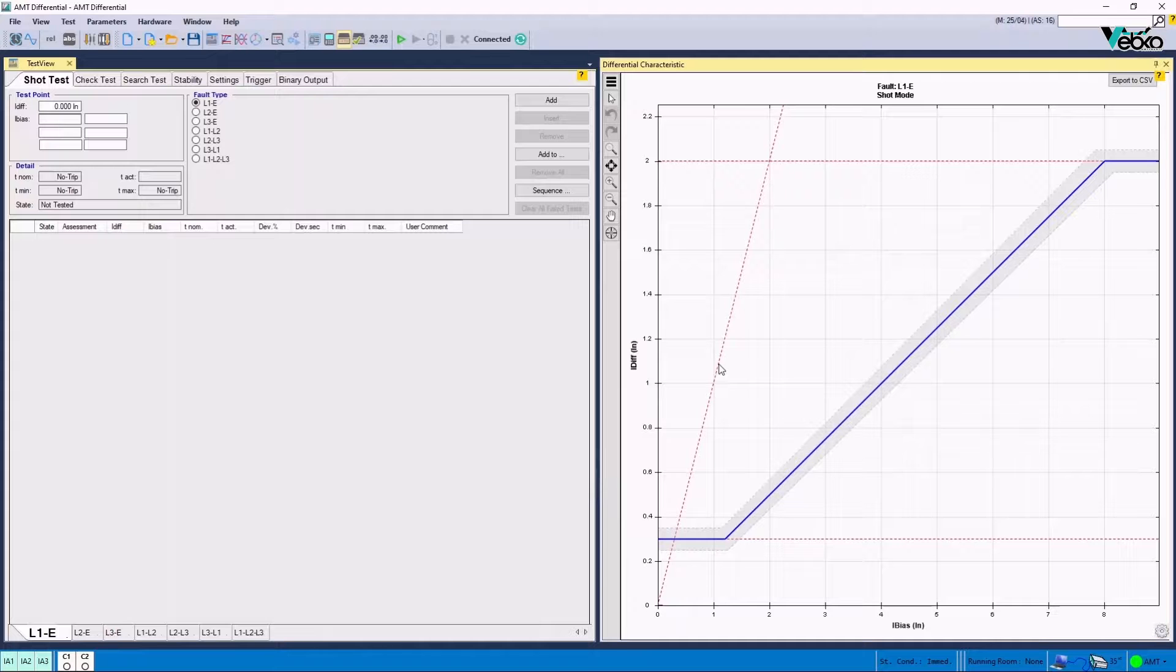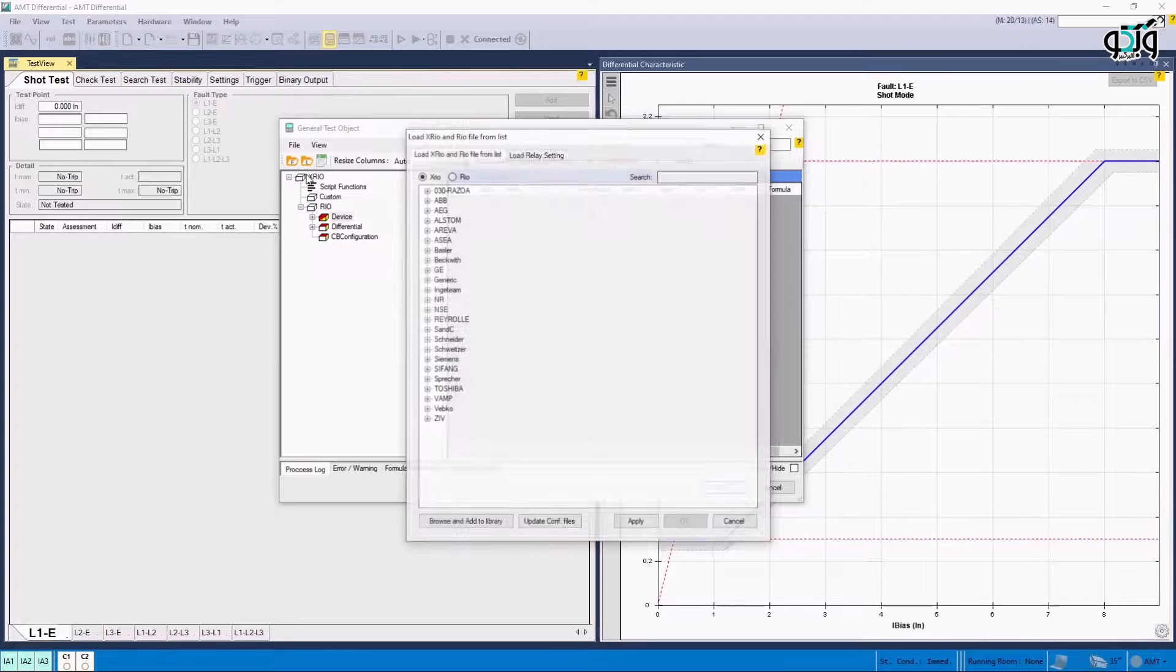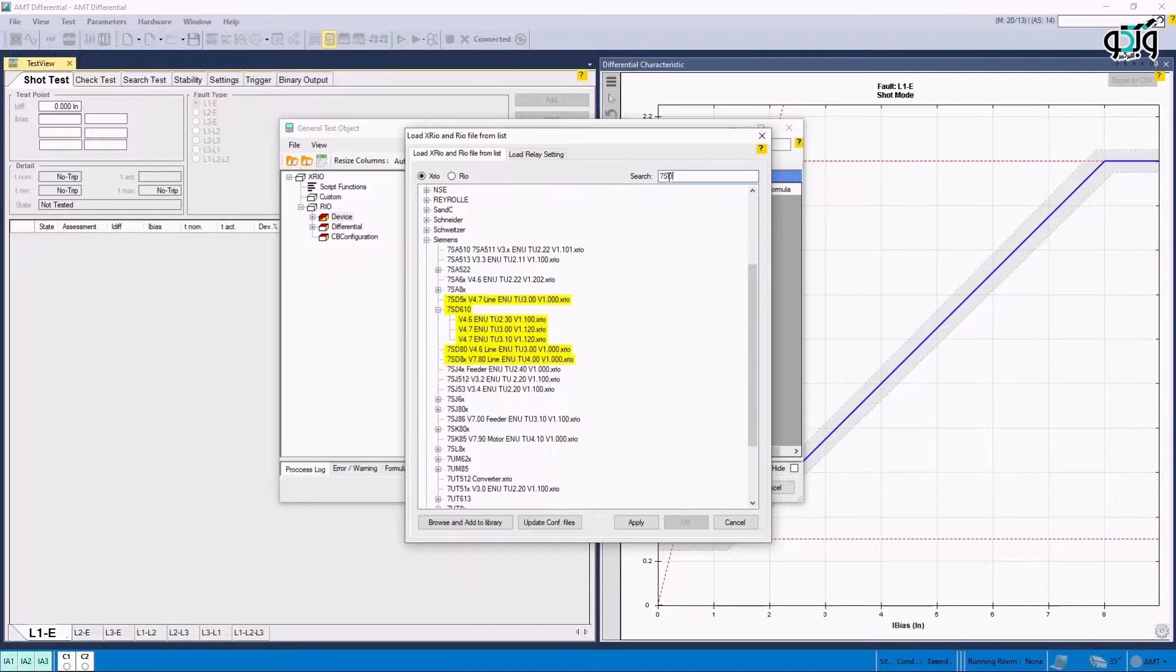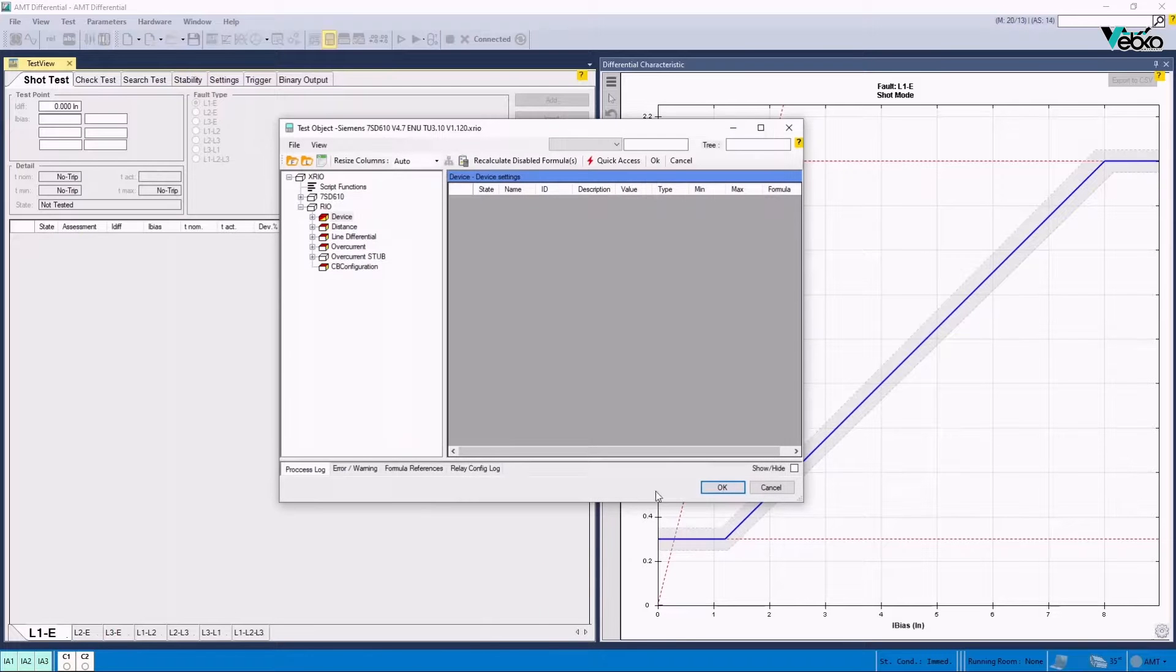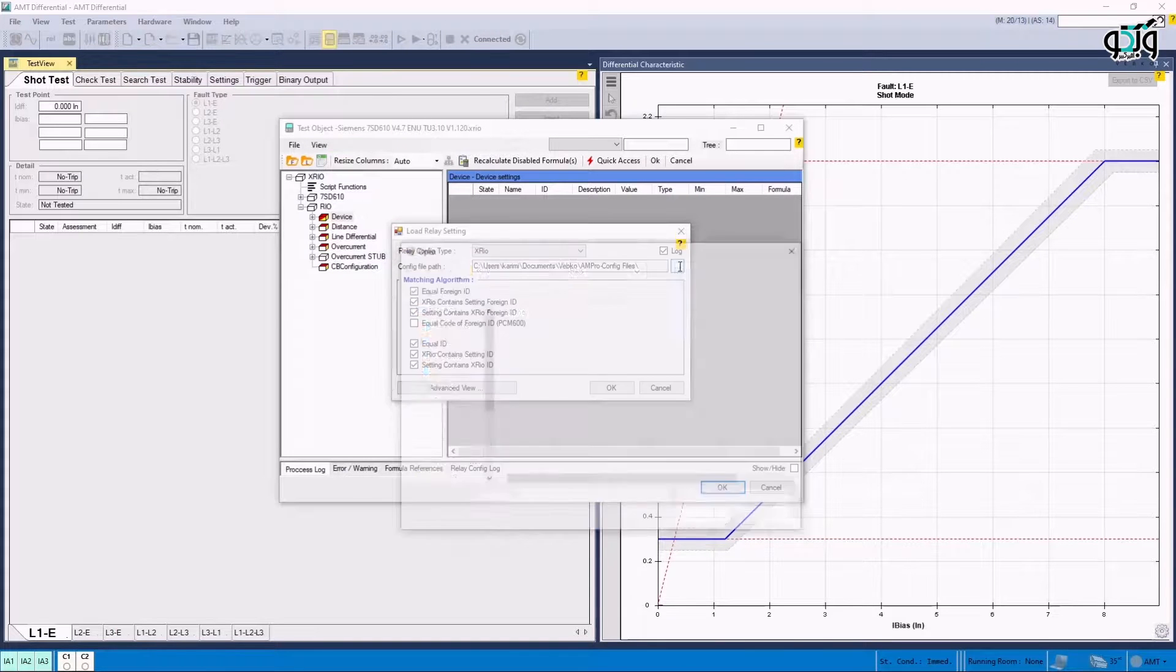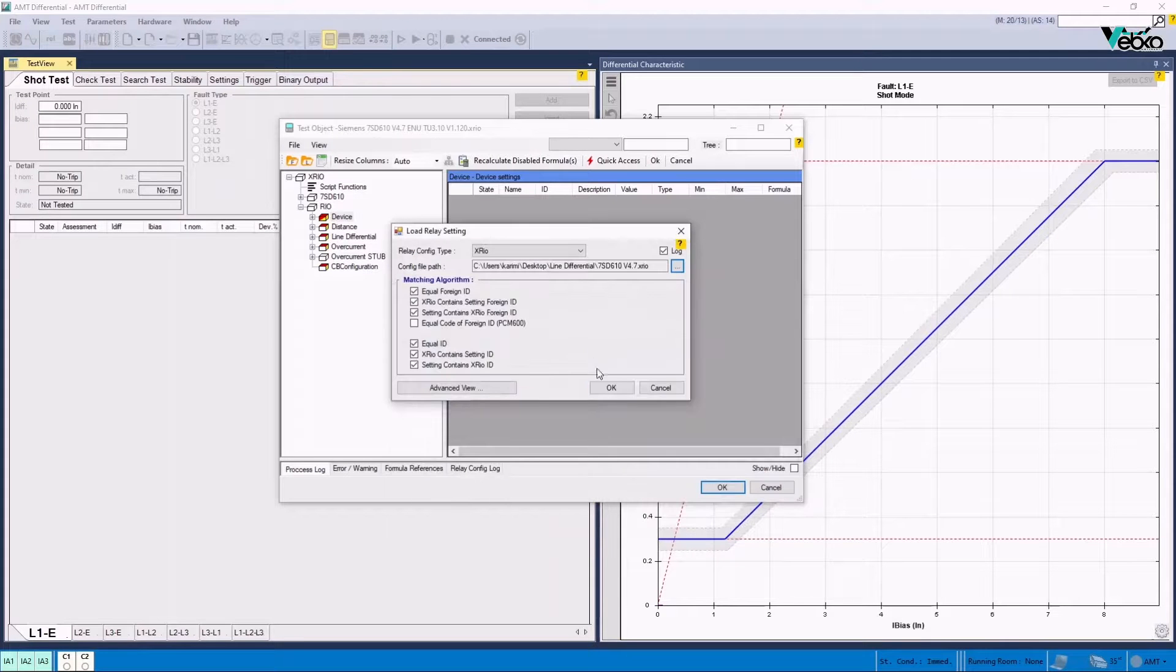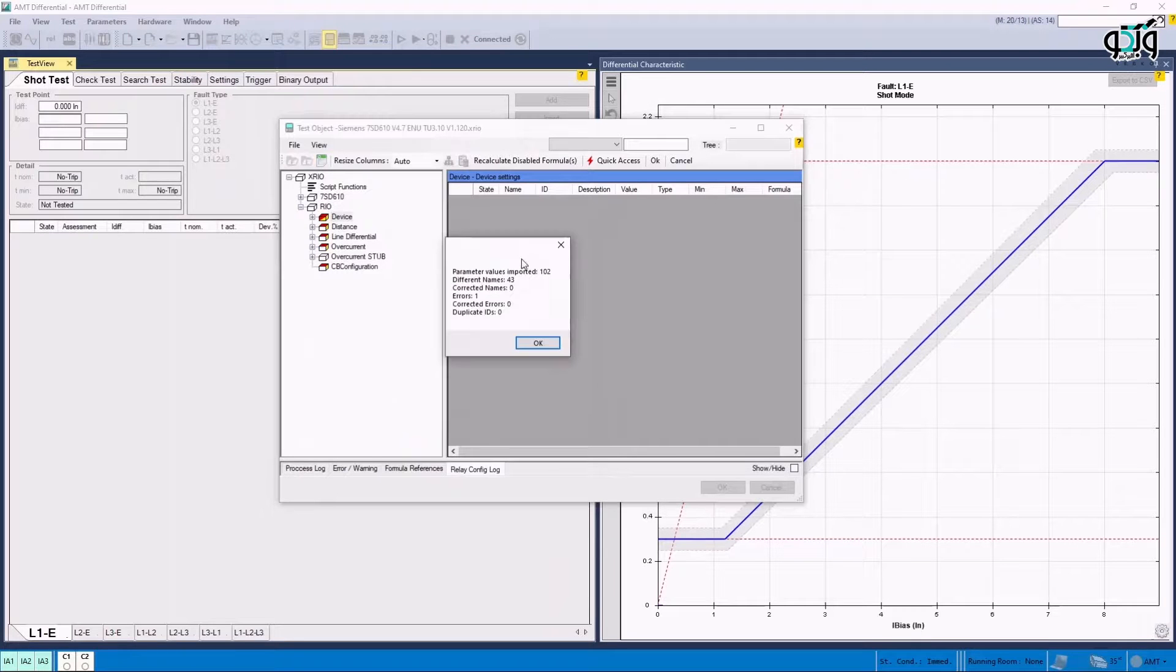Now by clicking on Test Object Parameters option, Import from List option, from the file menu or the icon labeled L letter is selected. In this section, by entering the relay name in search box, it is possible to select the XRIO or RIO corresponding to that relay and the software version. Here, 7SD61 is entered. By double-clicking on the related XRIO file menu and then Load Relay Setting is selected. In Relay Config Type section, the configuration type received from the relay is selected which is different from every brand. In Config File Path section, the path of this file is given to the software. Here we are receiving the XRIO file using DIGSI 4 software of Siemens company.